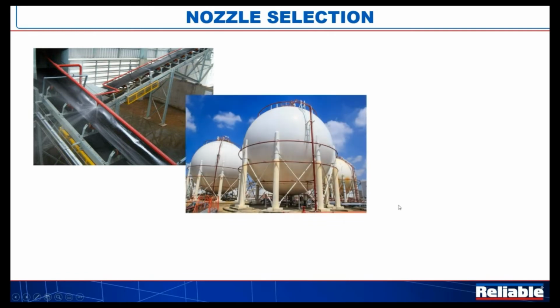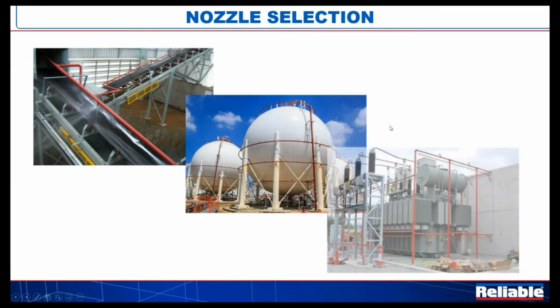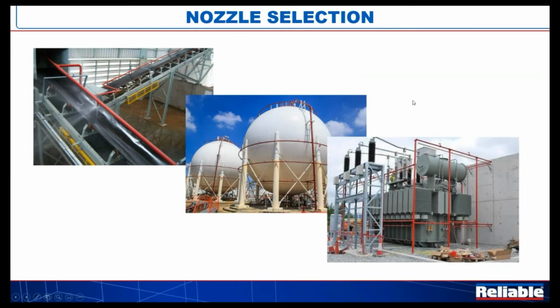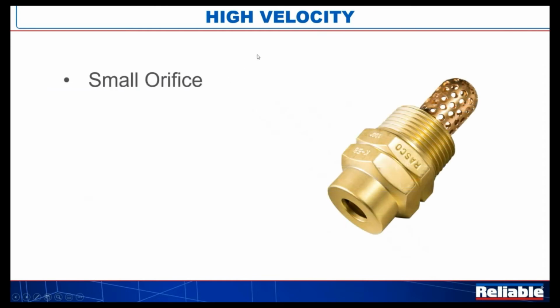If we're doing cooling, protecting from exposure fire, we have a little different mechanism of fire control, and we're going to typically use a medium velocity nozzle. Again, we'll talk about why that is in a second. And then finally, for some of the heavier oils, we're going to use the high velocity nozzles. So let's take a look at the differences. We'll work our way backwards, back from the high velocity. These are typically characterized by small orifices.